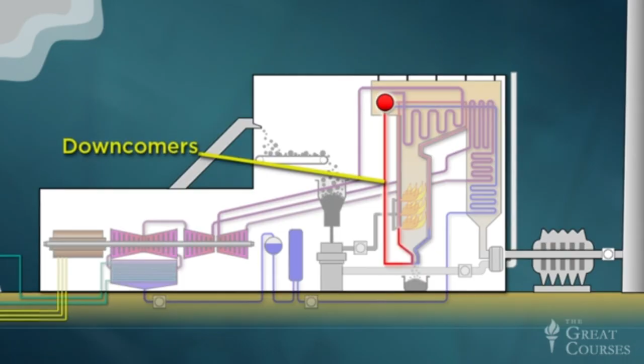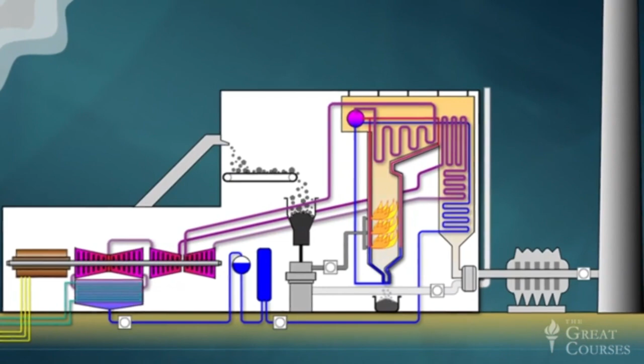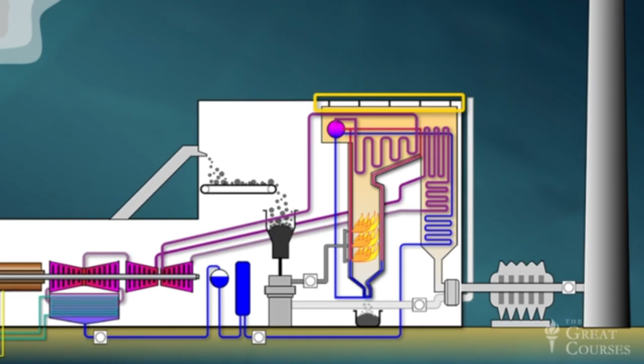Meanwhile, the separated water is circulated from the steam drum back down to the bottom of the furnace through pipes called downcomers. And then it's fed back into the risers where the generation of steam continues. This massive assembly of risers, downcomers, and steam drums isn't supported on the floor of the plant. It actually hangs from a structure overhead to allow for the thermal expansion and contraction of the pipes through their huge range of operating temperatures.